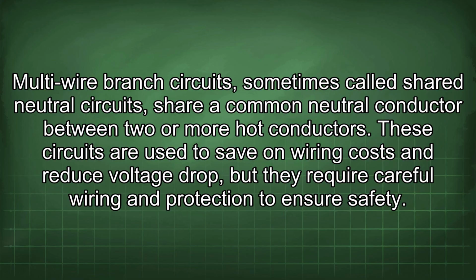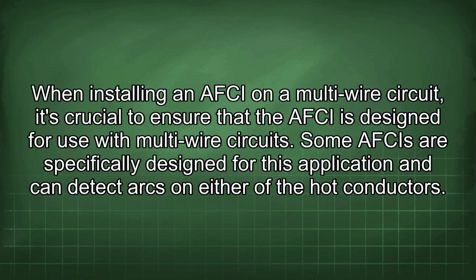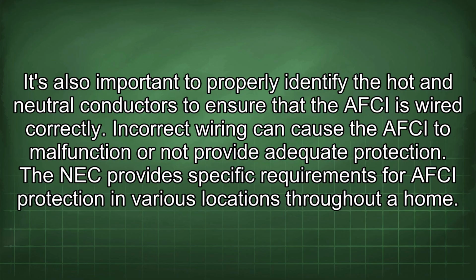to ensure safety. When installing an AFCI on a multi-wire circuit, it's crucial to ensure that the AFCI is designed for use with multi-wire circuits. Some AFCIs are specifically designed for this application and can detect arcs on either of the hot conductors. It's also important to properly identify the hot and neutral conductors to ensure that the AFCI is wired correctly. Incorrect wiring can cause the AFCI to malfunction or not provide adequate protection.